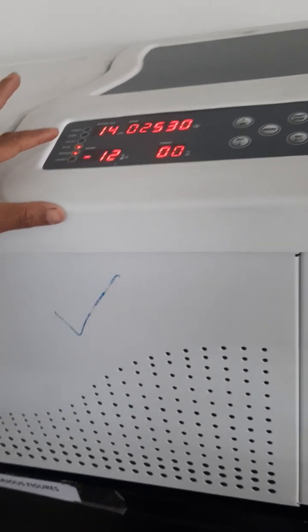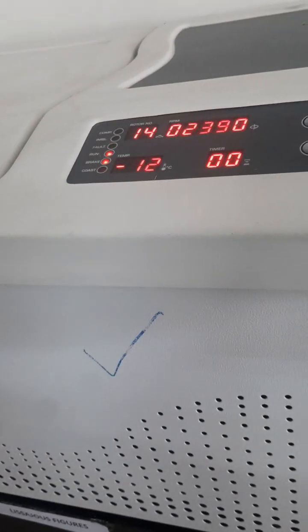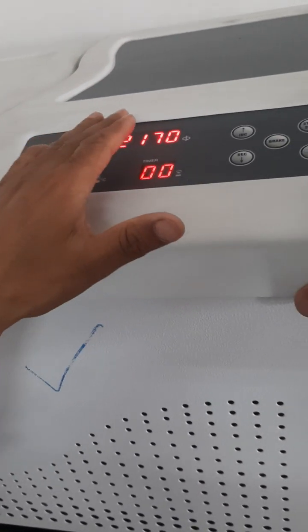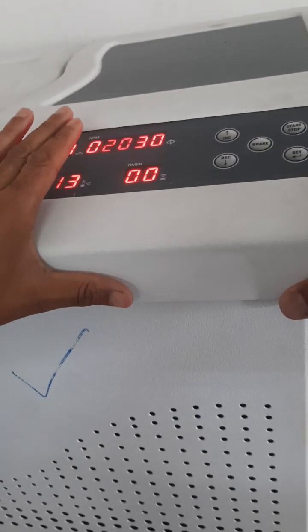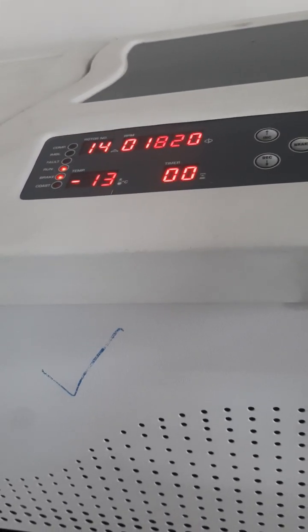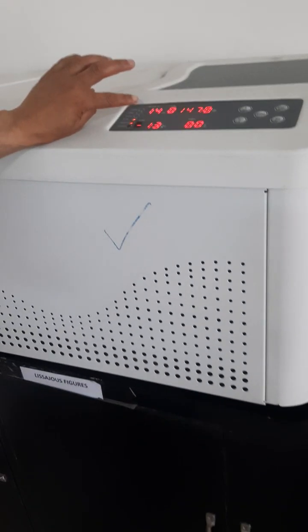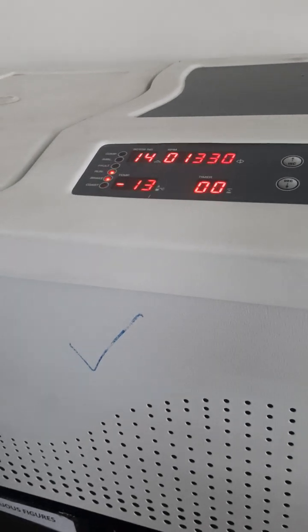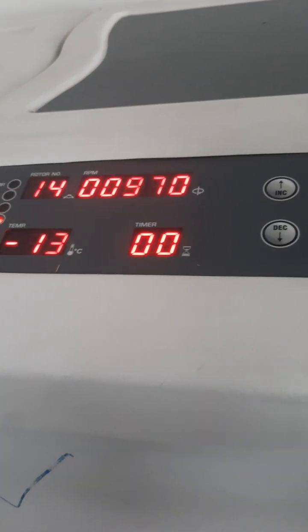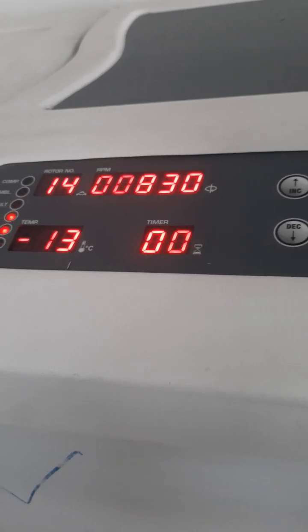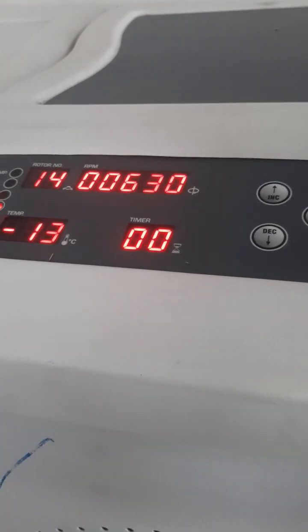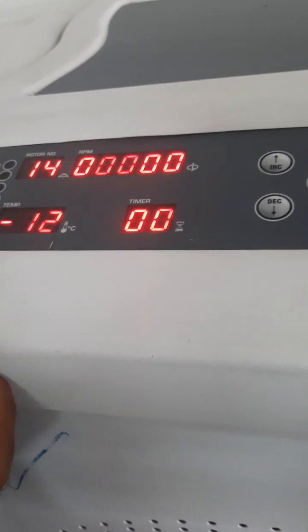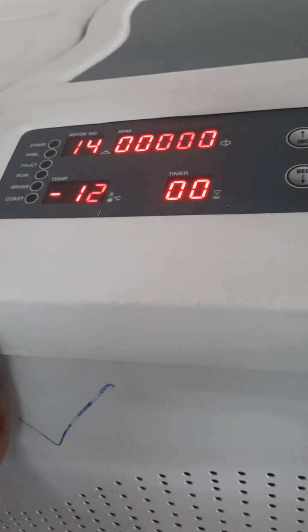Machine is still running, but it is decelerating, that is, it is going to 0 rotations per minute. So at 0 rotations per minute, we will try to open the lid when the compression is released. The compression has just gone. There is no pressure now, but we will wait for the rotation to come down to 0. Or we can check whether we can open the lid. The lid is not opening until the rotation reaches 0 and the compression is fully released.